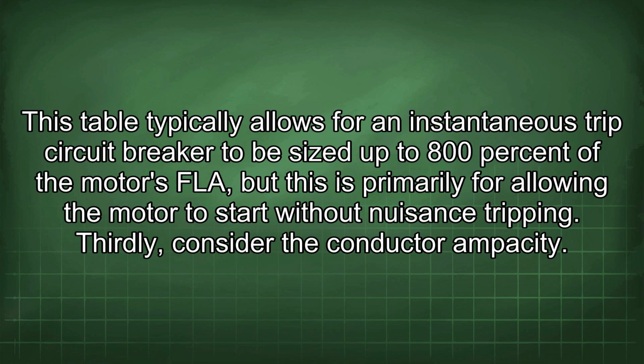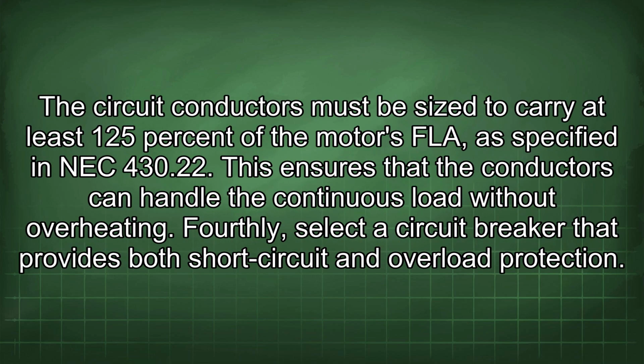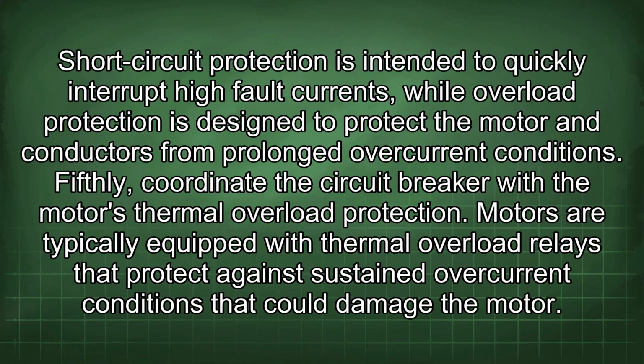Thirdly, consider the conductor ampacity. The circuit conductors must be sized to carry at least 125% of the motor's FLA, as specified in NEC 430.22. This ensures that the conductors can handle the continuous load without overheating. Fourthly, select a circuit breaker that provides both short circuit and overload protection. Short circuit protection is intended to quickly interrupt high fault currents, while overload protection is designed to protect the motor and conductors from prolonged overcurrent conditions.